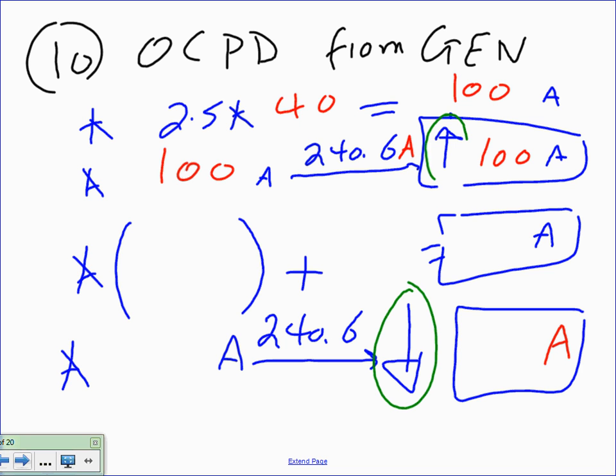That's step one. Step two, you add that big fat fluffy 100 here to the full load current of the other motor. This is, guys, like sizing an overcurrent protection device for a feeder of multiple motors. On the generator side, exactly the same. So that will give you 111 if I did my math right. And from 111, you take the same thing to 240.6A, and you have to go down because it's a feeder, and that will get you 110, Chris, or less, 110.